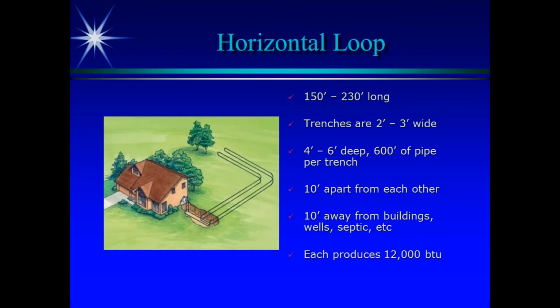They start fighting with each other. So again, 10 feet away from the buildings, the wells, and the septic. Why? If I put a loop too close to the basement, people have asked me, there's heat that goes out from my basement, so why not snuggle right up next to the basement and take that? What sense does that make? I'd be taking from the basement the heat that I'm turning around and putting right back into the basement. So we want to make sure we get far enough away so that we aren't stealing the energy from the building that we're actually trying to put energy into.